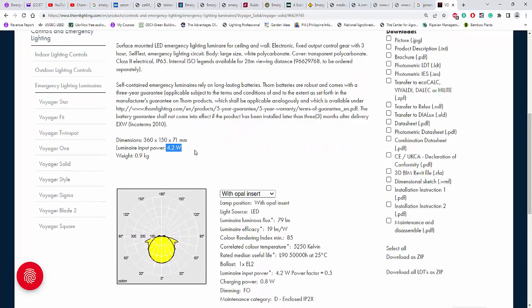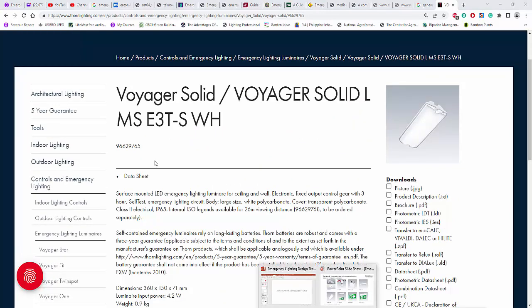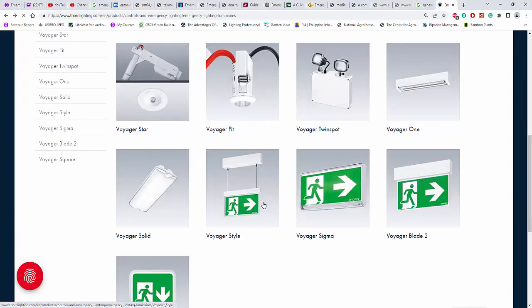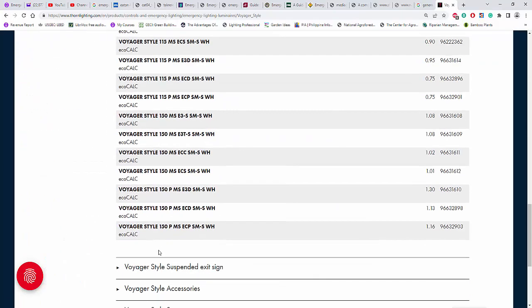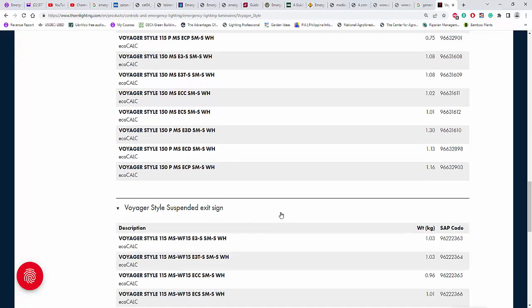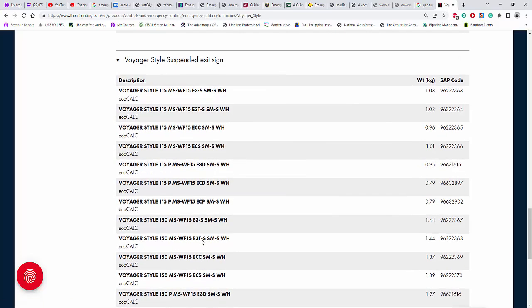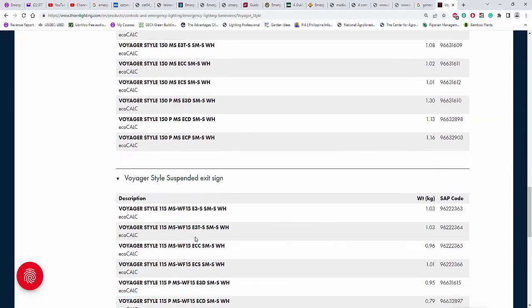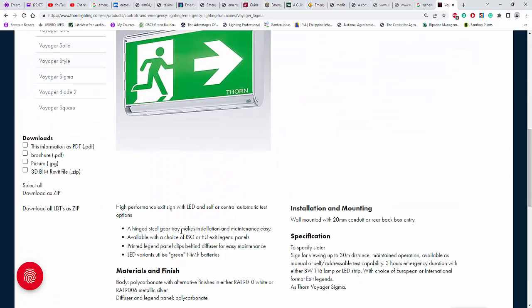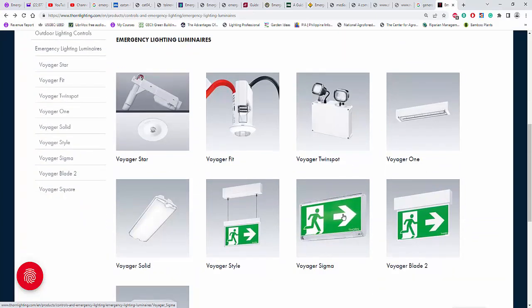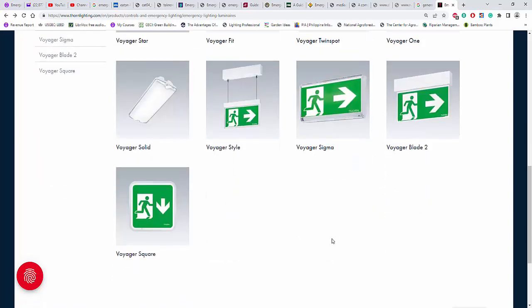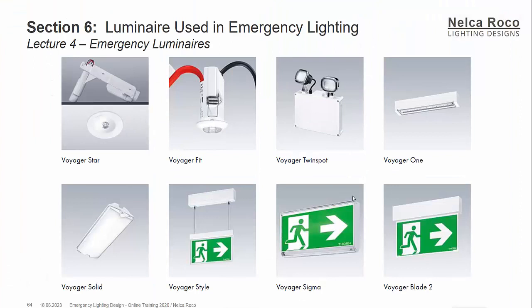Let's go and check the exit signs — if they also have a photometric file. For this suspended one, it doesn't have one. Why is that? Because sometimes it is illuminated from outside, and sometimes illuminated from inside. Because the sticker is there, we cannot see the photometric because it's blocking the sticker. This other one also doesn't have a photometric file. Everything that has a sticker outside cannot be calculated because the luminous flux will be blocked by the stickers.